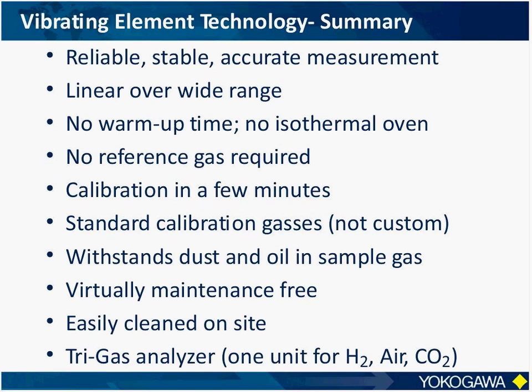Just a brief summary about the vibrating element technology. It's proven itself in the field to be a reliable, stable, and accurate measurement. It is linear over a very wide range. It does not require an isothermal condition, so there are no ovens or heaters, no warm-up time associated with it. No reference gas is required. Calibration can be performed in just a few minutes after the instrument is turned on, since there's no warm-up time. We're able to use standard calibration gases. We don't have to fool with custom blended specialty gases that may be fairly expensive.